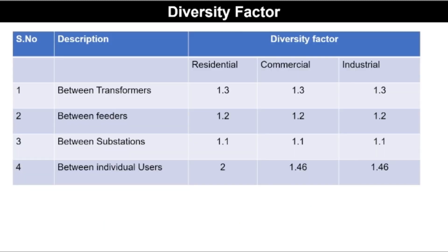The diversity factor of various buildings: between transformers, whether the area is residential, commercial, or industrial, the diversity factor is 1.3. Between feeders, whether residential, commercial, or industrial, it is 1.2. At the subsidiary substation level it is 1.1. Between individual users, it is 2.0 for residential, 1.46 for commercial, and 1.46 for industrial cases.